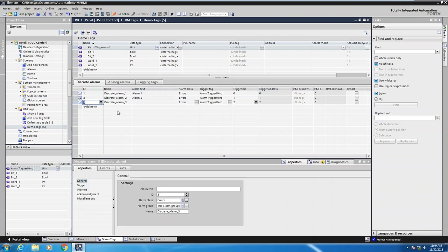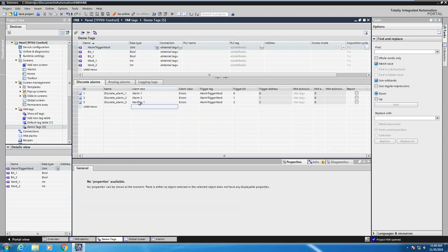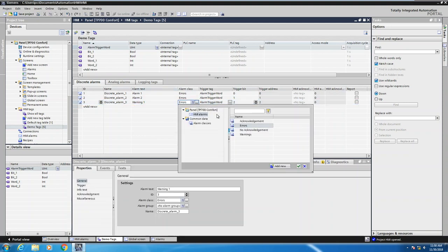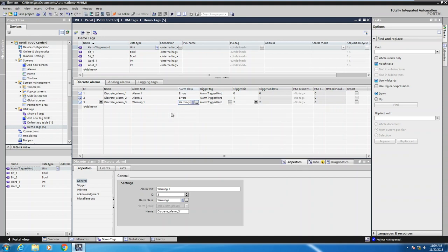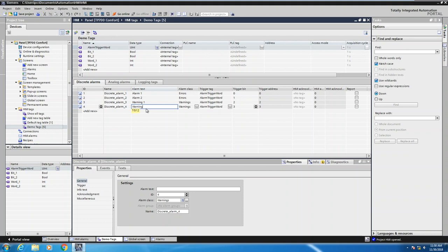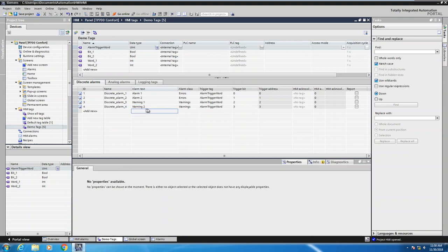Next, I'm going to add another alarm. This time the text is going to be Warning 1, because I'm going to create a few warning conditions. For the alarm class, I can do table editing up here — so instead of Errors, I'm going to select Warnings. This message or alarm condition will not require any acknowledgement. I'll add one more and call it Warning 2. So now I've got four different alarm conditions: two errors and two warnings.